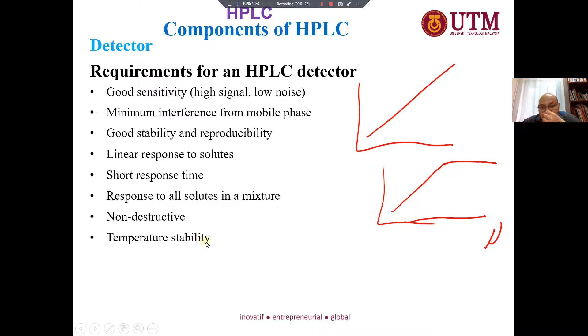Linear response to solute. Okay, what is meant by linear response to solute? As the concentration increases, the detection also increases. We don't want the concentration to increase and then the response reaches a limit. We want it as linear as possible. We need a very short response time so it can give you a better reading. It should respond to all solutes in a mixture so it can detect as many kinds of analytes as it can. If possible, the detector should also be non-destructive, and have temperature stability.